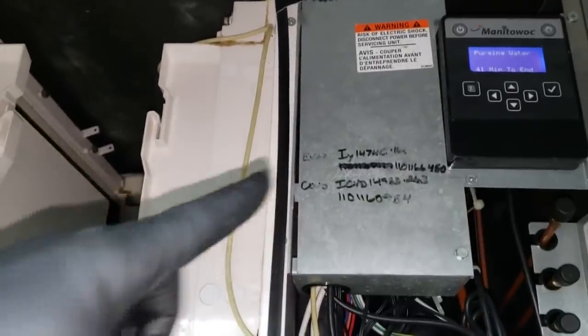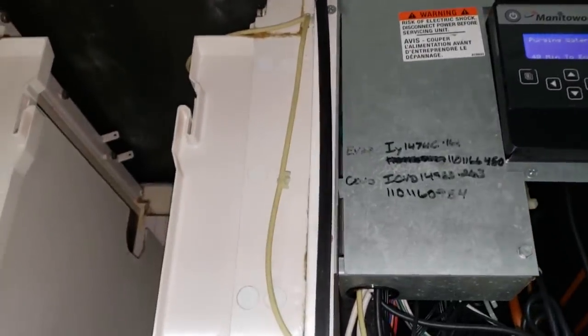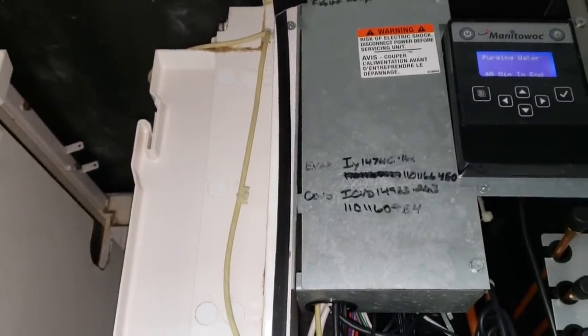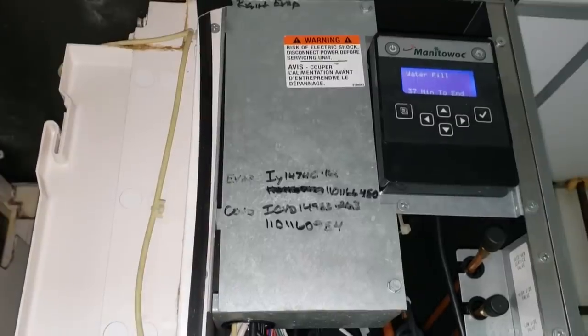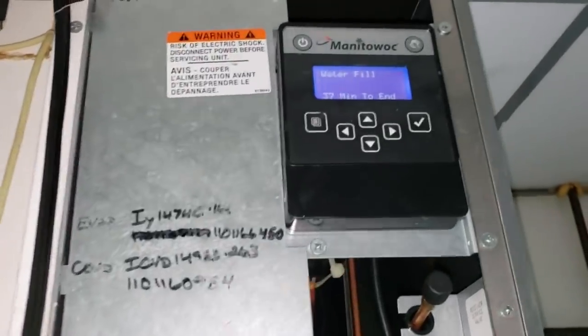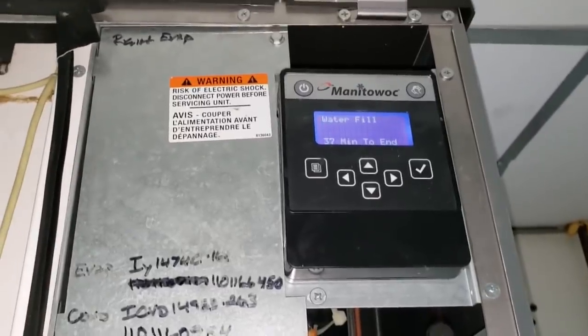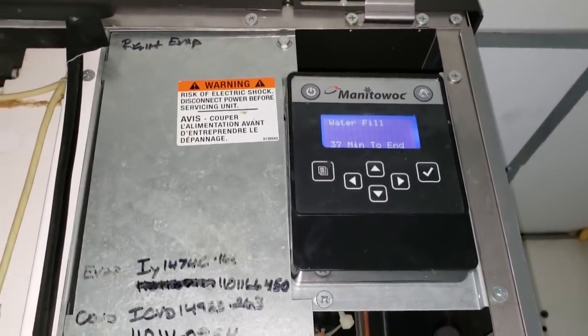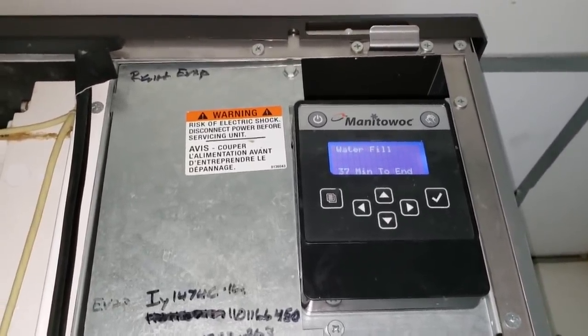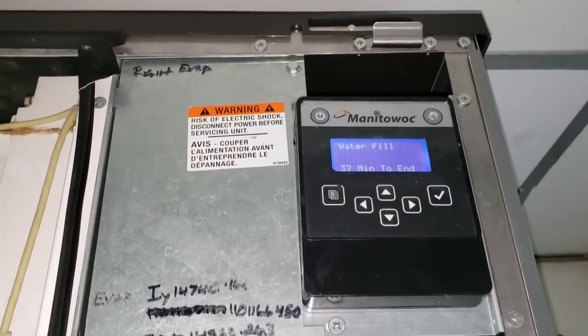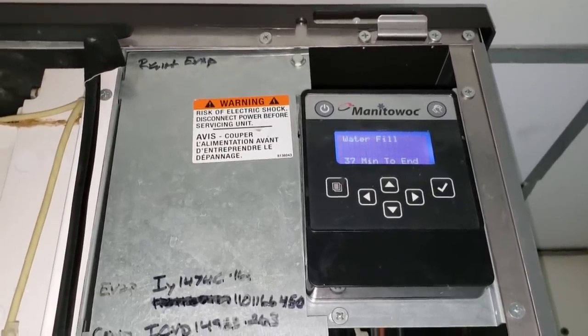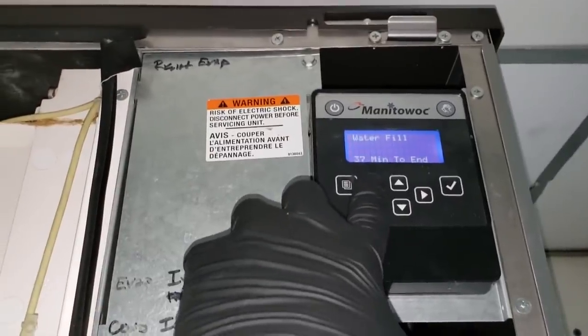The first thing it does on a clean cycle is it purges all the dirty water out, so you don't want to add cleaner to start because you'll have a problem. So it is technically safe to add cleaner right now because we're in the water fill cycle. If you know the sequence of operation of a cleaning, it dumps first, then when the water fill's done, it tells you to add cleaner. After the water fill, it's going to circulate for a set amount of time. That 37 minutes is the total time.